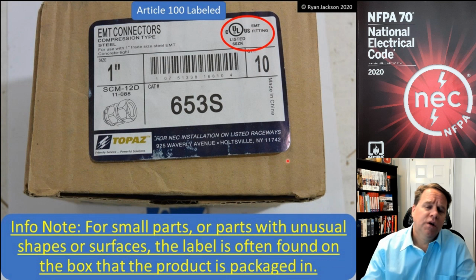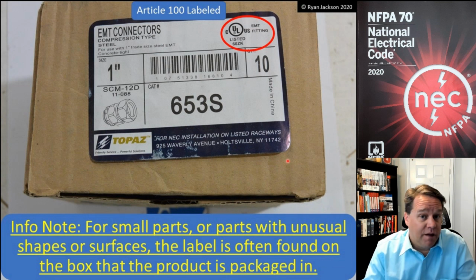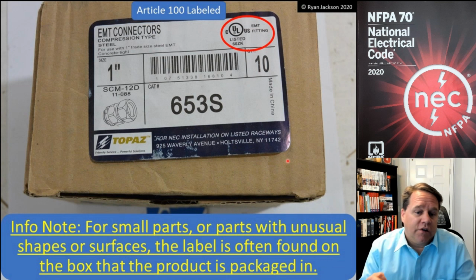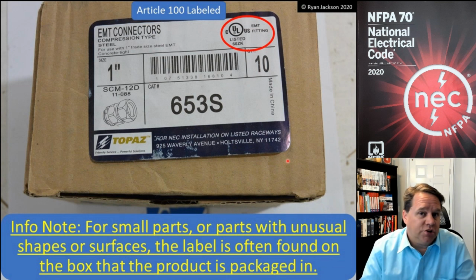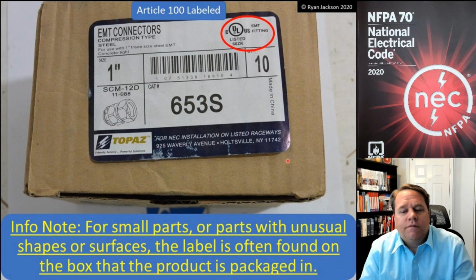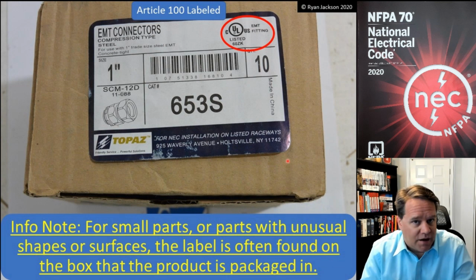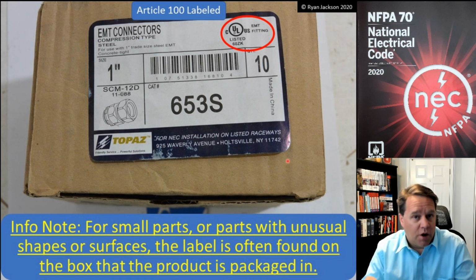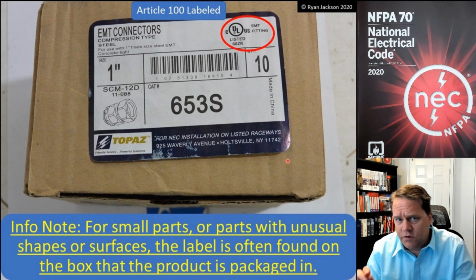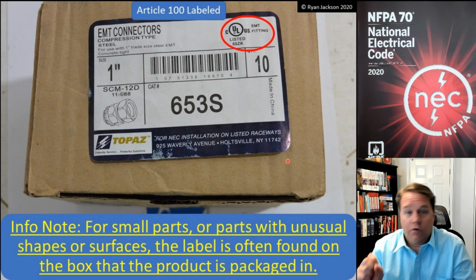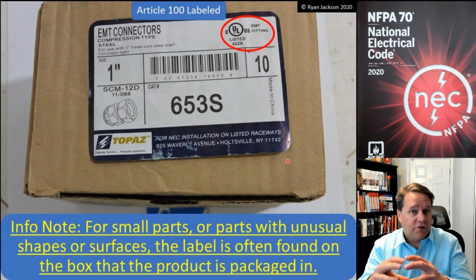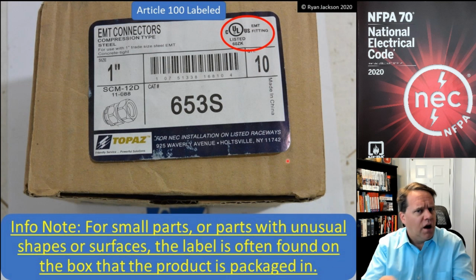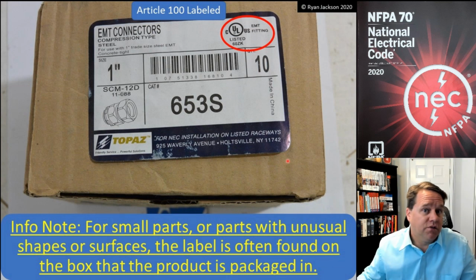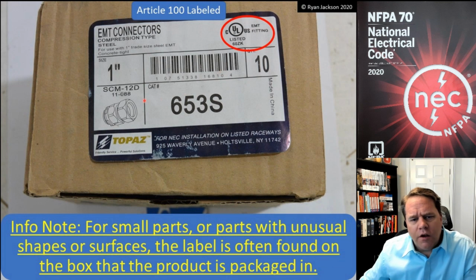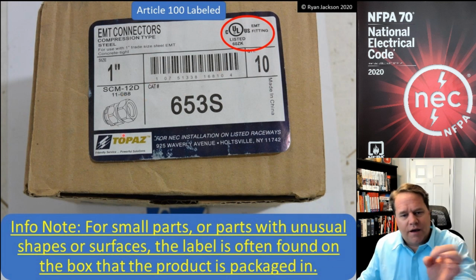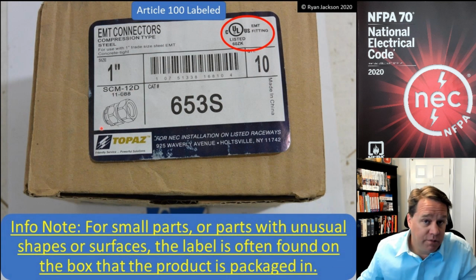In the 2020 code, they added an informational note to the definition of labeled, which I think was quite good. It just tells us, look, for small parts or parts with unusual shapes or surfaces, the label is often found on the box that the product is packaged in. And in fact, if you go to UL Product IQ, it'll tell you where to find the label. It might say that it's either on the product itself or in the smallest shipping container, I think is what they call it. So the smallest box that they can put it in. So you're not going to find an actual embossed mark on each of these compression connectors.